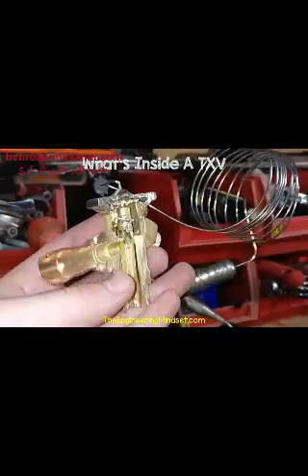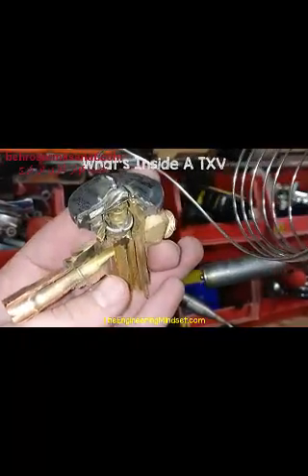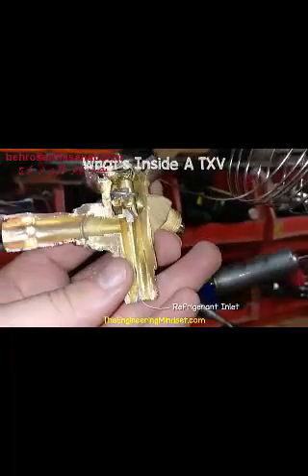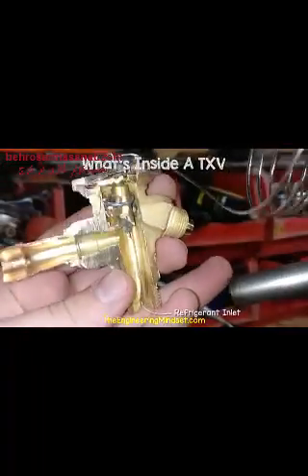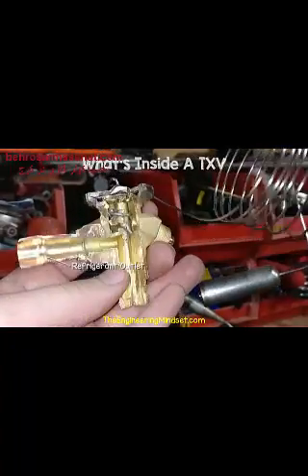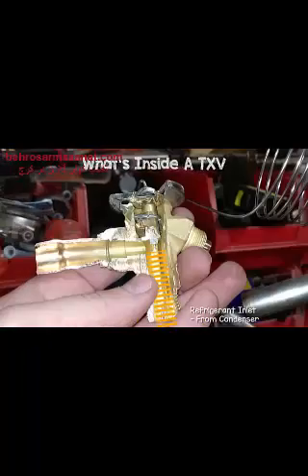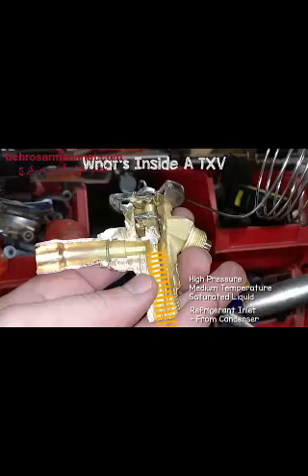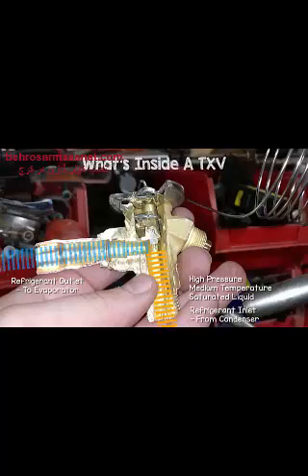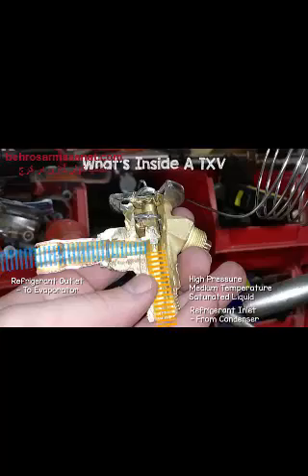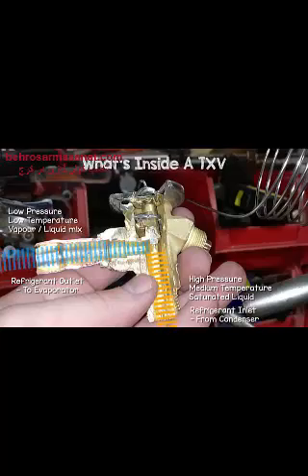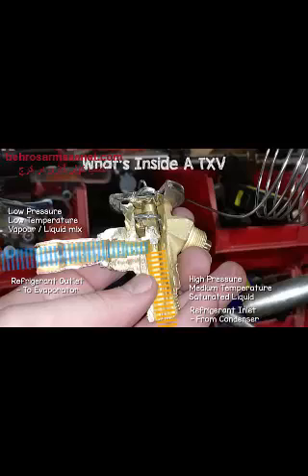So we have the main body which holds everything together. We have the refrigerant inlet coming in from the bottom of the main body in this vertical pipe, and then the refrigerant outlet on this horizontal pipe. So the refrigerant comes from the condenser and enters the valve body via the inlet. It enters as a high pressure, medium temperature saturated liquid. It then passes through the valve body, and when it leaves, it exits the valve through the outlet and will now be a low pressure, low temperature liquid vapor mixture.